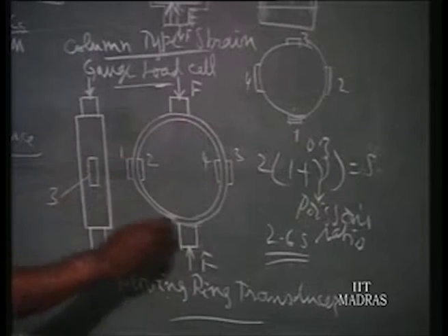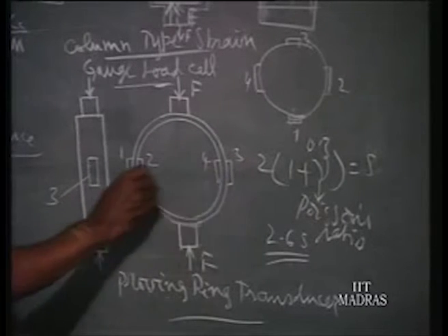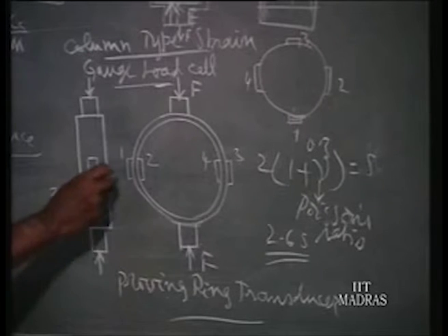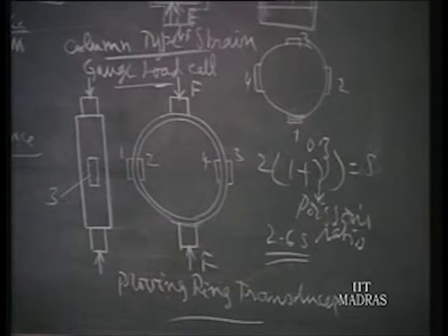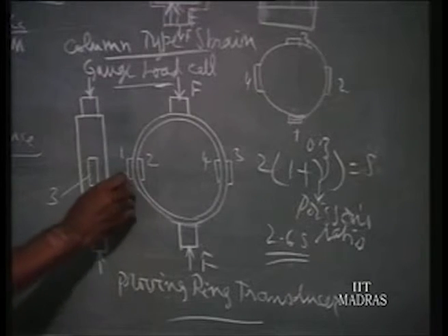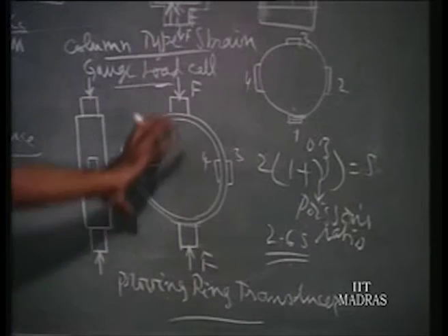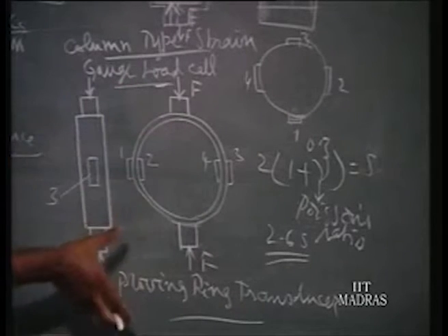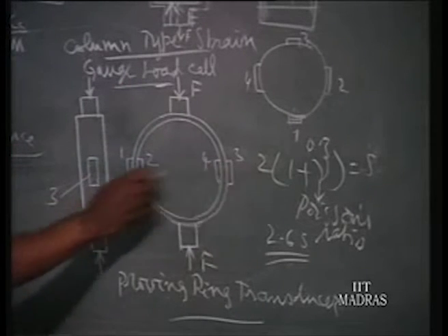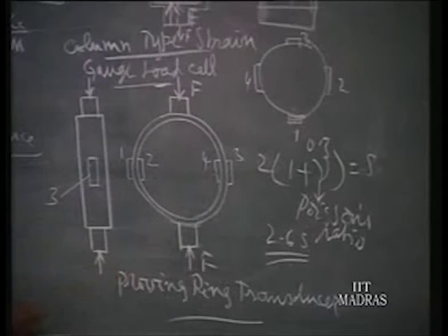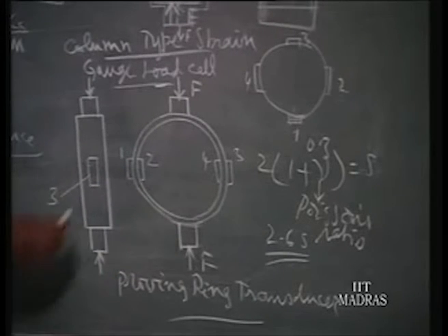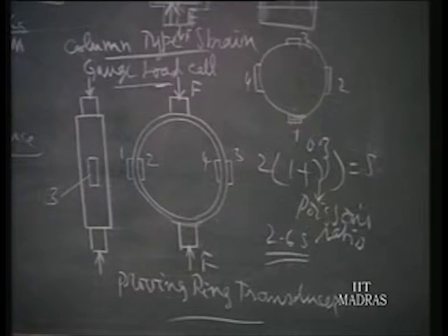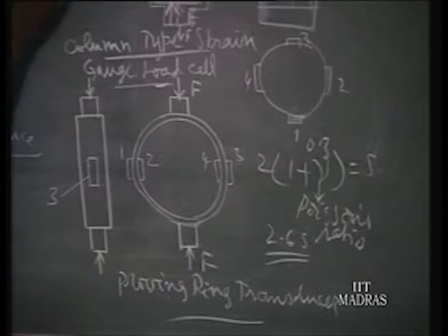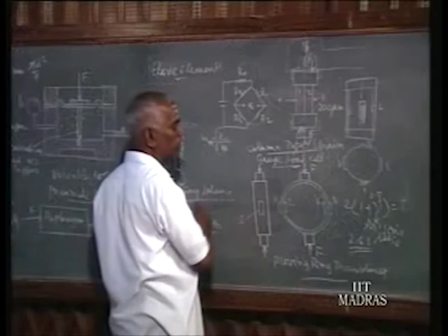It is made up of just a ring, and on the inside and outside surfaces we paste the four strain gauges as shown here, and this is the end view of it. So you find when the load is applied, the ring is compressed. This compressive load is converted into bending strains: surfaces 1 and 3 will be subjected to tensile strain, 2 and 4 will be subjected to compressive strain. Then the same bridge holds good, 1 and 3 tensile, 2 and 4 in compression. So the same bridge we can use.